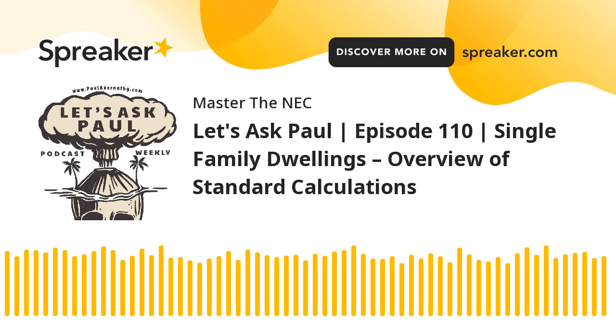Now, here's what's important about that. For a one family dwelling, it's 3 VA per square foot, but even the individual dwelling units in a multifamily building, which we cover in our course in Unit 11, where we get very deep into that, it's still 3 VA per square foot, okay? All right, so just wanted to make sure that you understand. 3 VA per square foot.